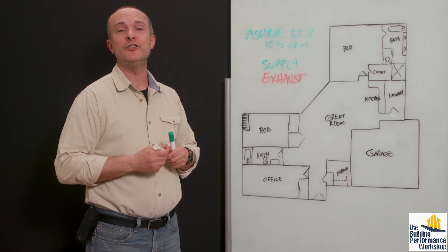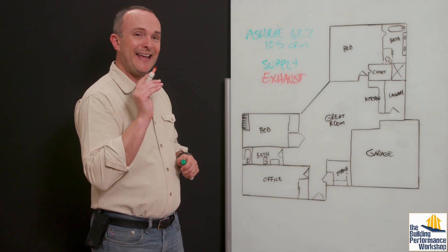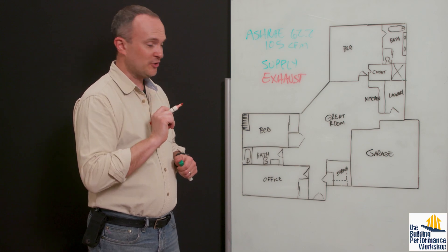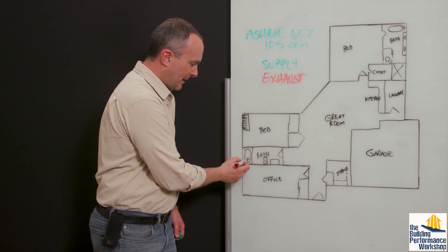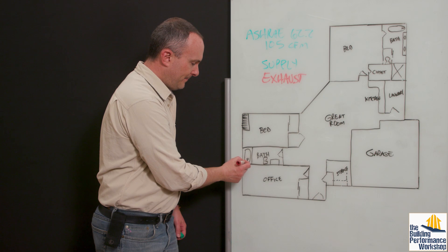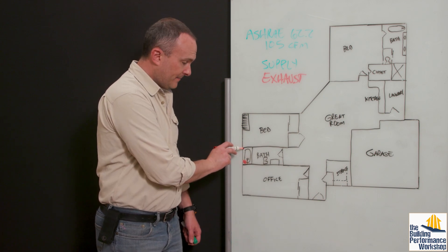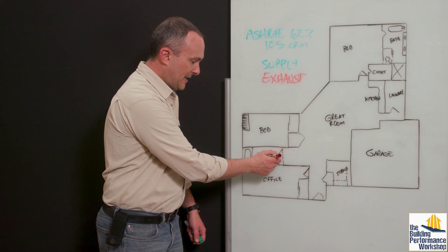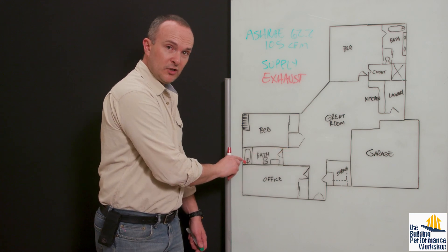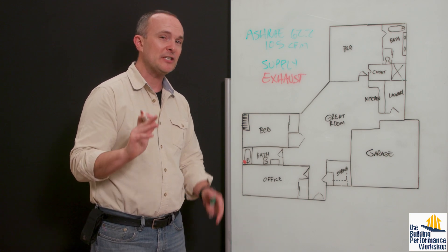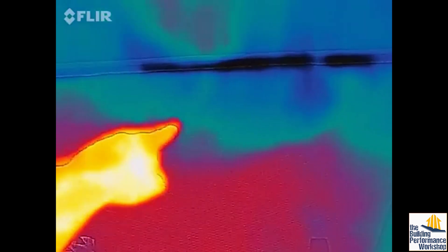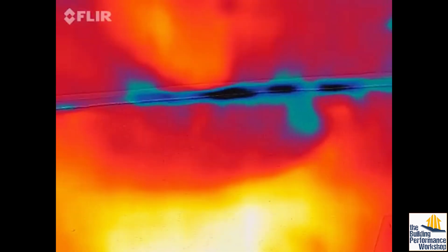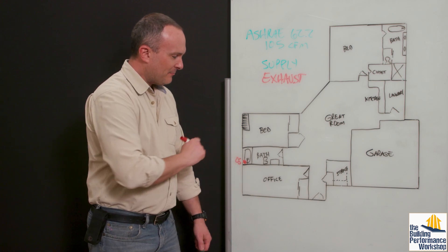So I put a pin in that and I also now do checking on the house's exhaust locations. So this bathroom is a perfect layout. I've got the door here. I've got the toilet between the door and the shower. I'm going to put my exhaust right there in that specific corner, not over here because the air will come in under the door and make a beeline for this exhaust port. And if you have not seen this happen in real life, it's hard to imagine that air actually follows a specific path, but I've literally seen air come into a house and take a 90 degree turn to rush toward the blower door that I've got set up somewhere else.